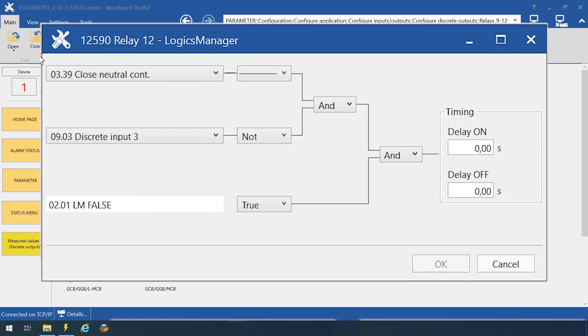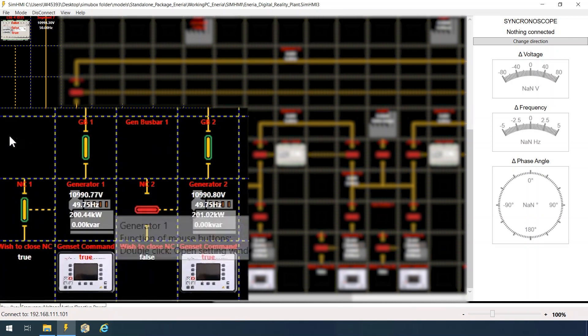Okay, back to simulation. Now, I am going to decouple our two generators from the grid. As you can see, the neutral contactor immediately closed and stayed only closed on the highest priority generator.